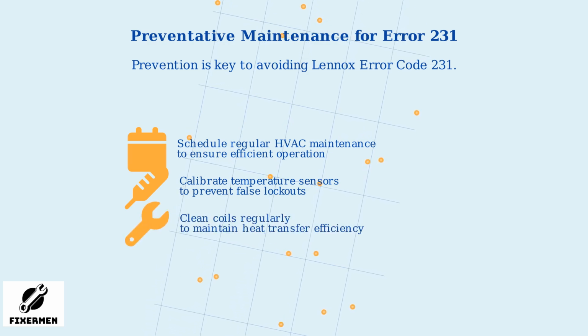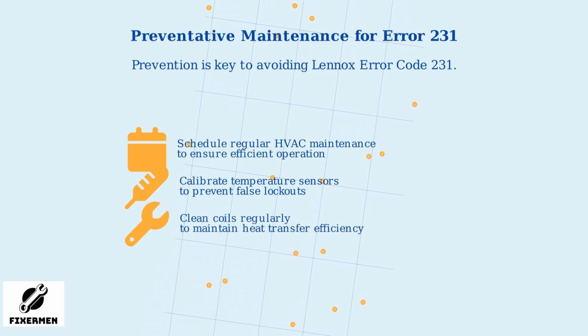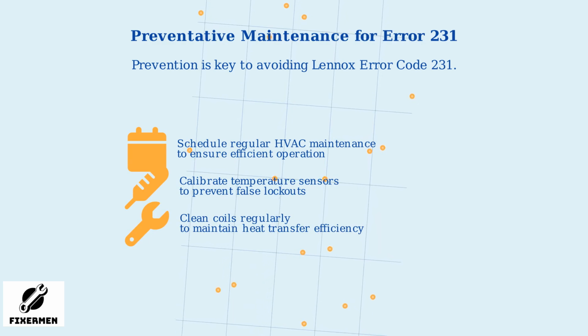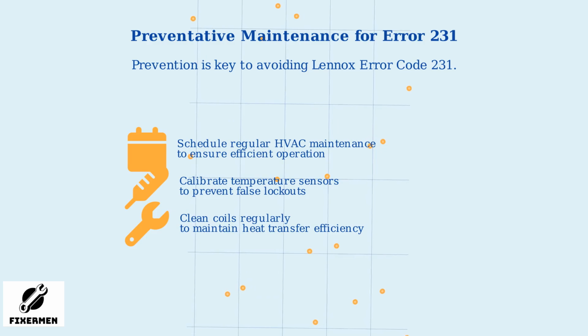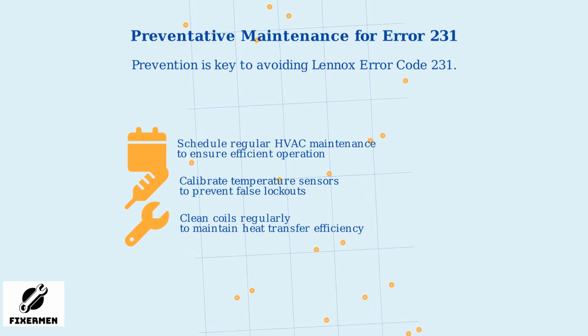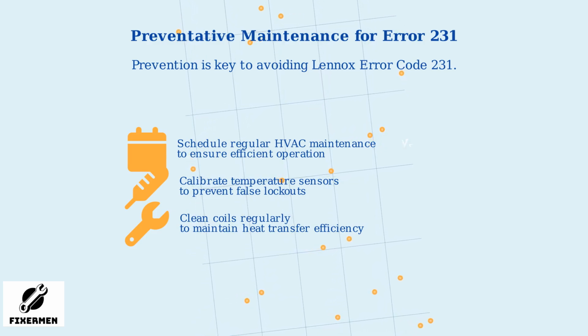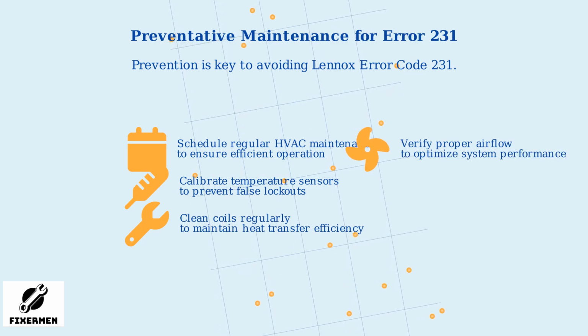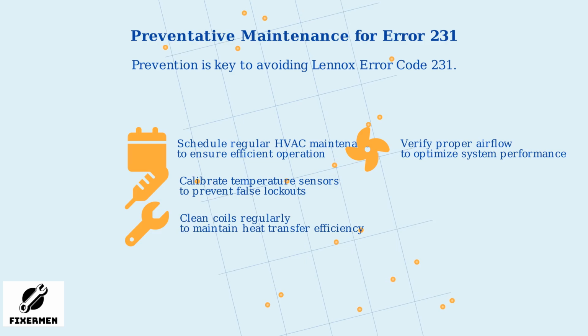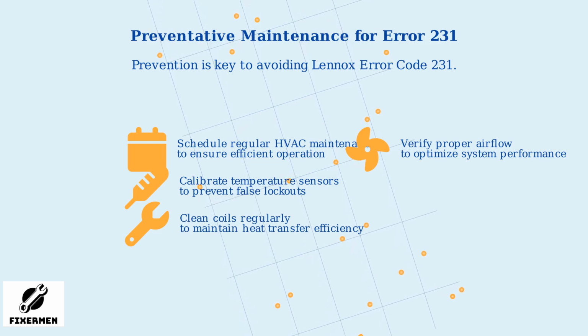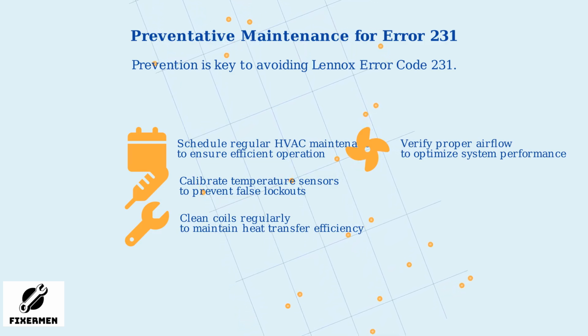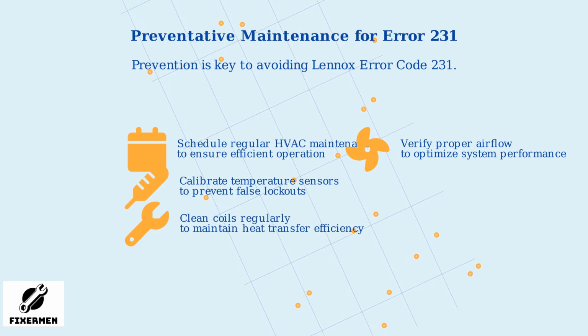Cleaning coils is another essential maintenance task. Dirty coils reduce heat transfer efficiency, making your system work harder and increasing the risk of lockouts during cold weather. Verifying proper airflow ensures optimal system performance. Blocked vents or dirty filters can restrict airflow, leading to inefficient operation and potential lockout conditions.